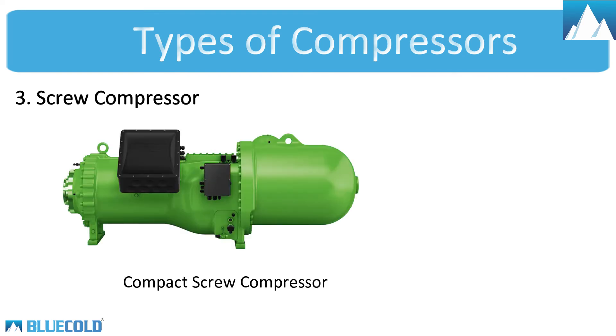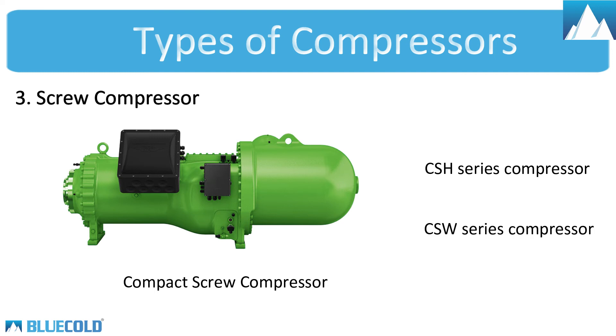Compact Screw Compressor — it's for industrial chiller systems. It has two different types: CSH Series, which can be used with both air-cooled and water-cooled condensers and can deliver temperatures up to minus 20 degrees Celsius; and CSW Series, which is used with a water-cooled condenser only and can deliver temperatures up to minus 10 degrees Celsius.